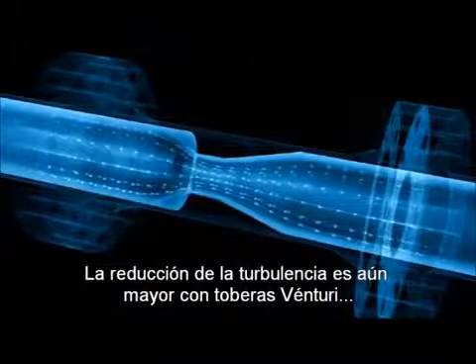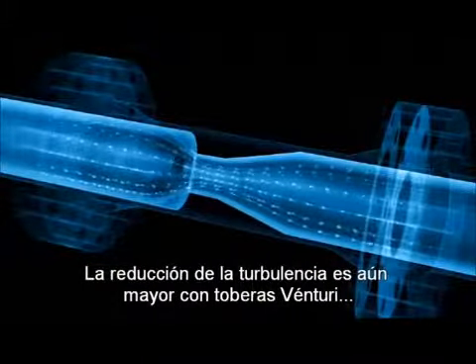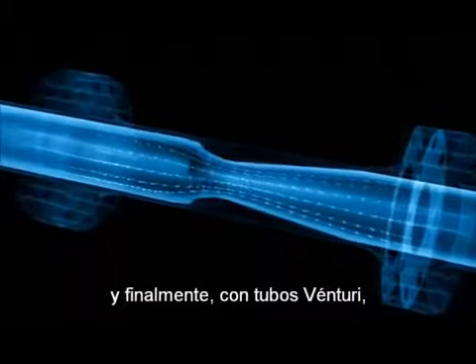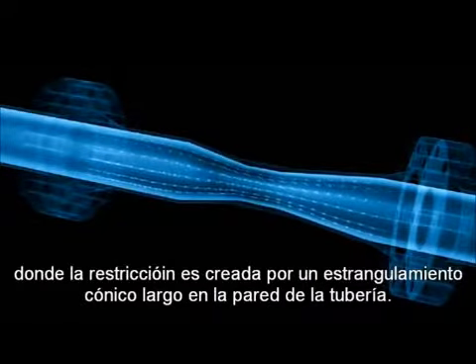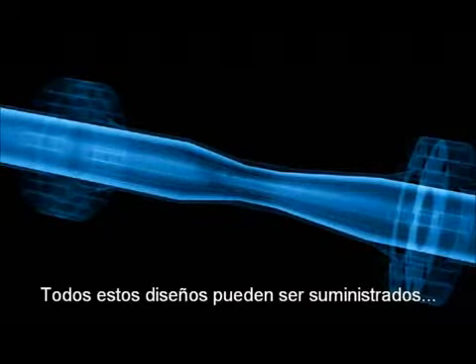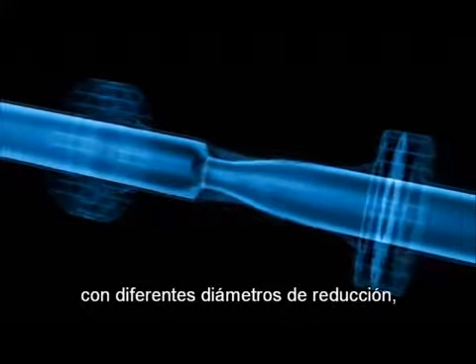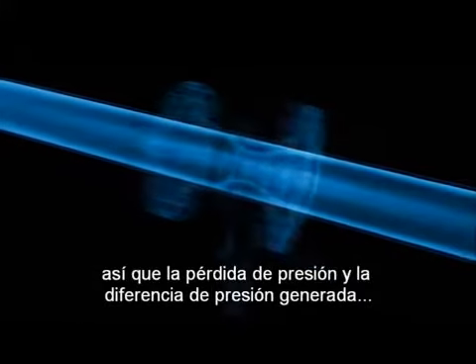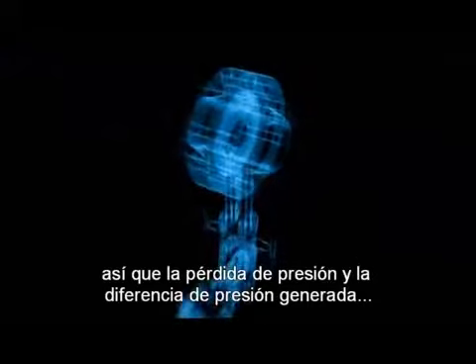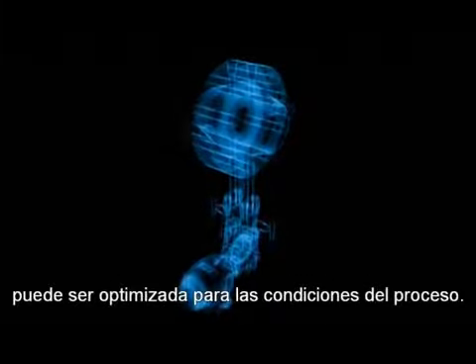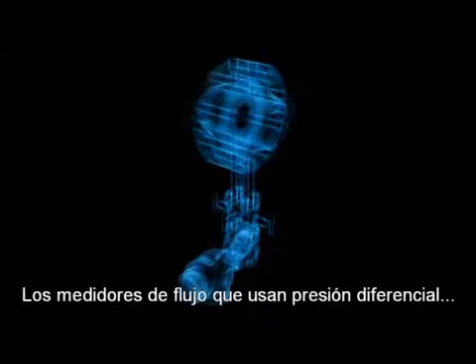Turbulence reduction is even greater with venturi nozzles, and finally with venturi tubes, where the restriction is created by longer conical constrictions in the pipe wall. All these designs can be supplied with different restriction diameter sizes, so that the pressure loss and the differential pressure generated can be optimized for the process conditions.